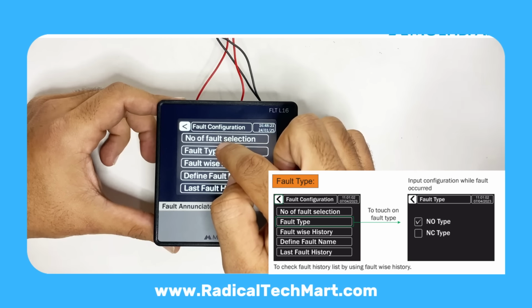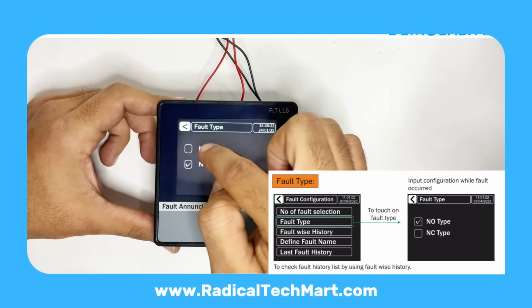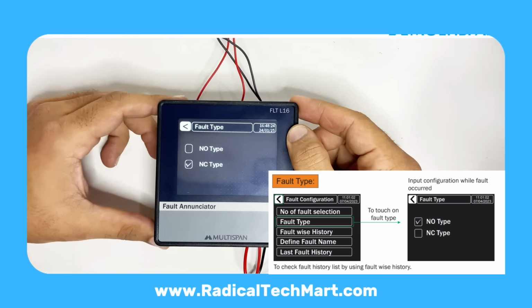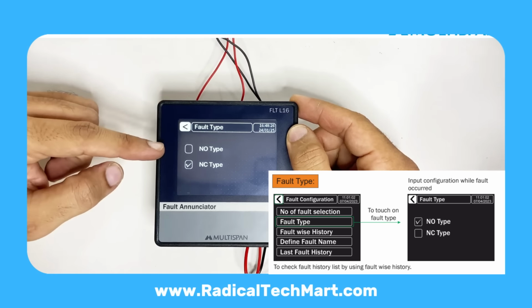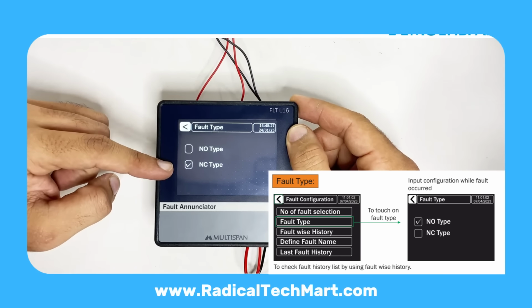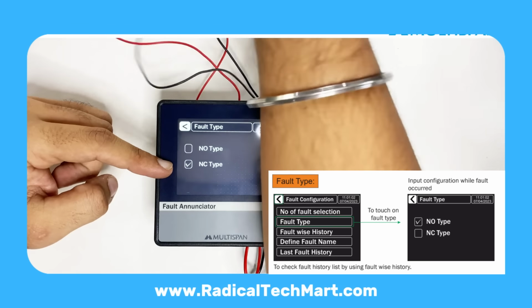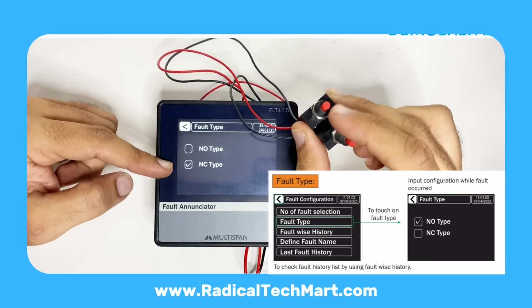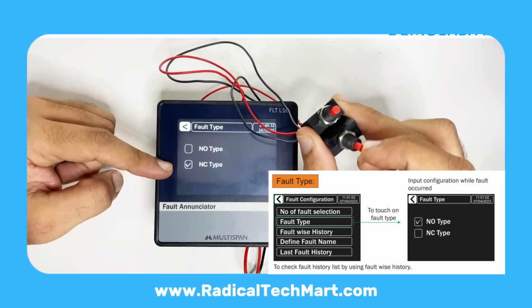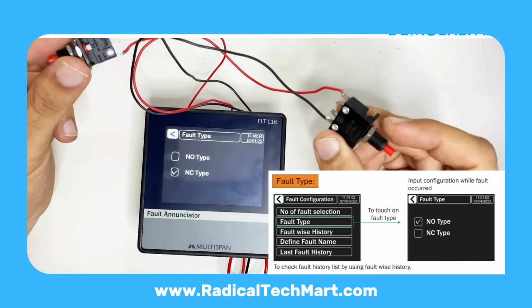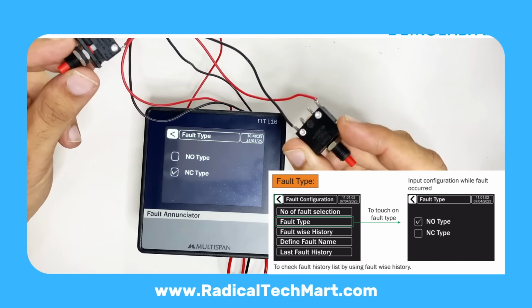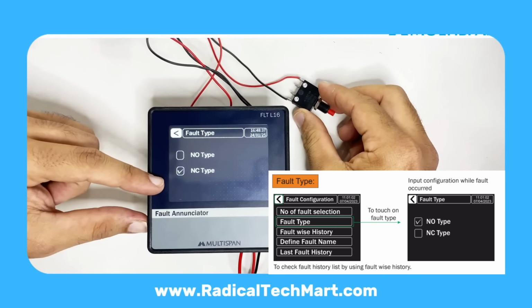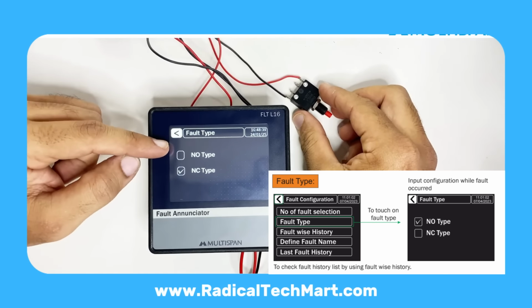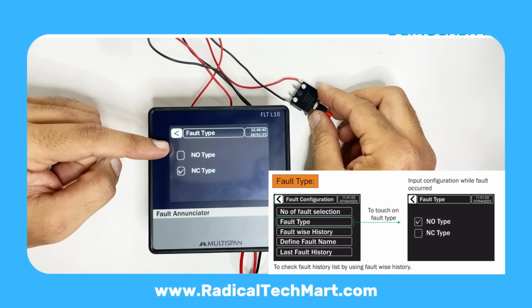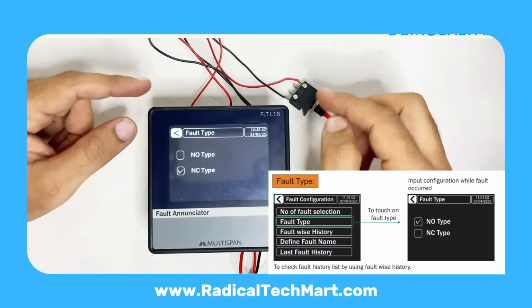Next option, fault type, NO, NC. Here you can define whether each fault input is NO or NC-type contact. In our demo, we are using NO-type switches, so whenever we press the switch, it creates an NC condition at the terminal and the annunciator detects a fault. If your field device gives NO contacts, you can select NO type here for that channel.